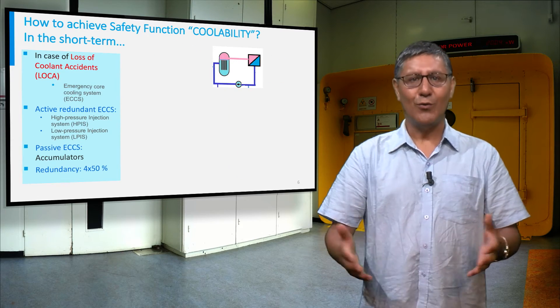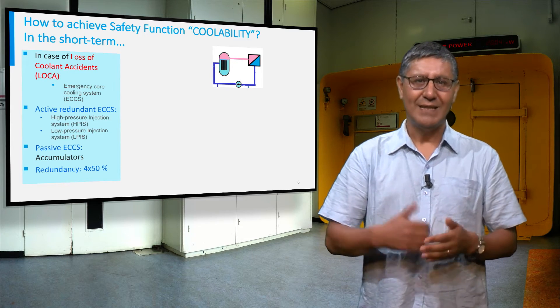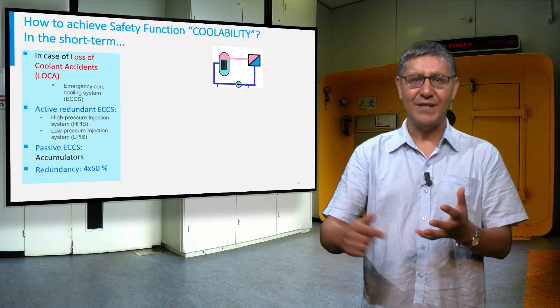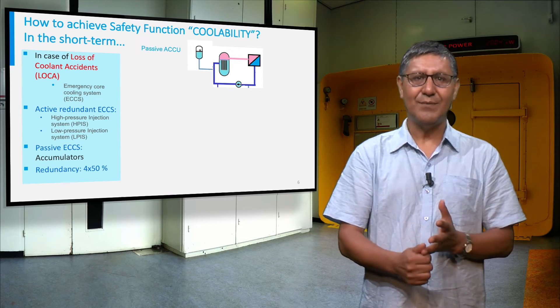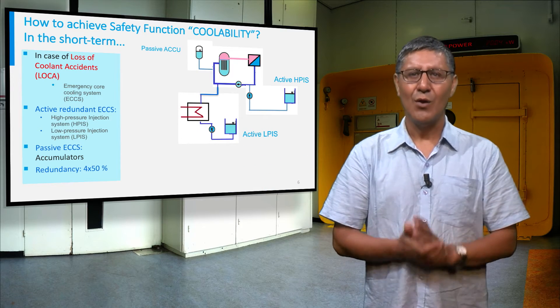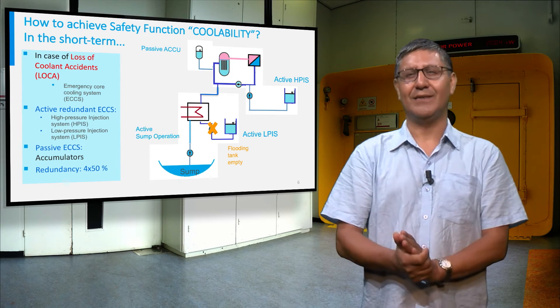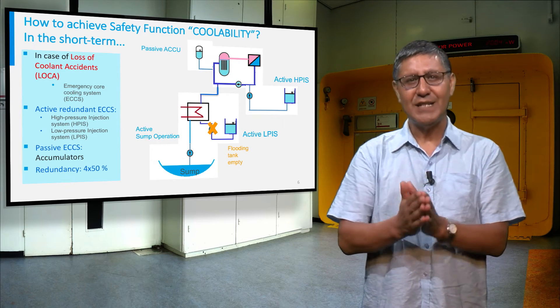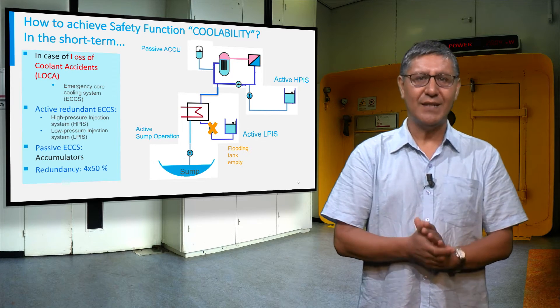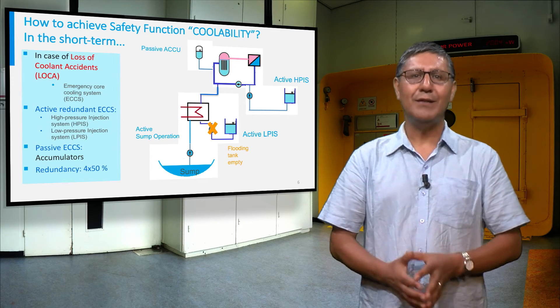An emergency core cooling system is used to ensure the coolability of the core in case of a loss-of-coolant accident. It consists of passive and active systems able to inject cold water into the core. All active systems take water from the flooding tank. It is a redundant system with four trains, each one with 50% capacity, meaning that only two systems are needed to ensure core coolability.